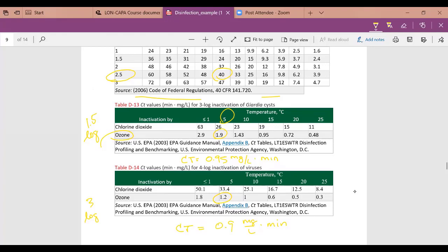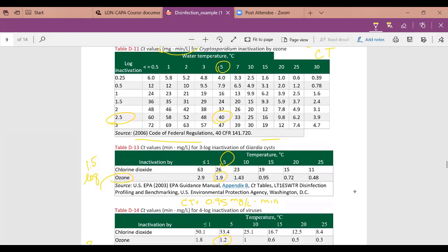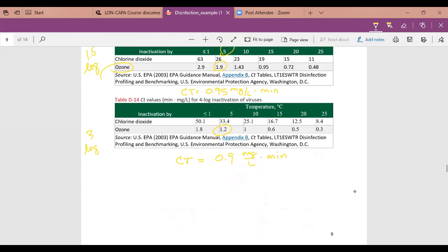Which organism controls disinfection? The one with the greatest CT requirement. In this case, cryptosporidium controls disinfection at CT = 40 mg/L·min. This also illustrates why New Zealand simply eliminated consideration of giardia and viruses and said to design the disinfection system based on crypto — because ozone for crypto gives the highest CT requirement at any temperature.